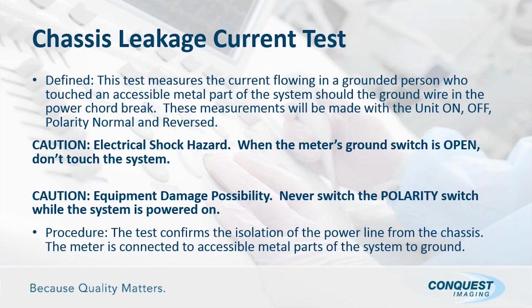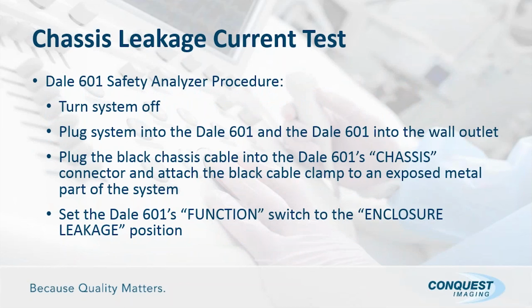So, what does that help us with? It confirms the isolation of the power line from the chassis, and the meter is connected to accessible metal parts of the system to ground. It says parts because they go on to define, later you'll see it in just a slide or two, where they want you to do the safety testing when using a Dale 601.